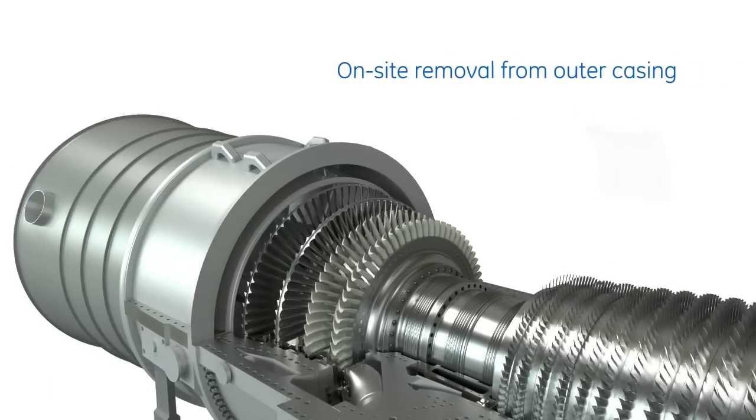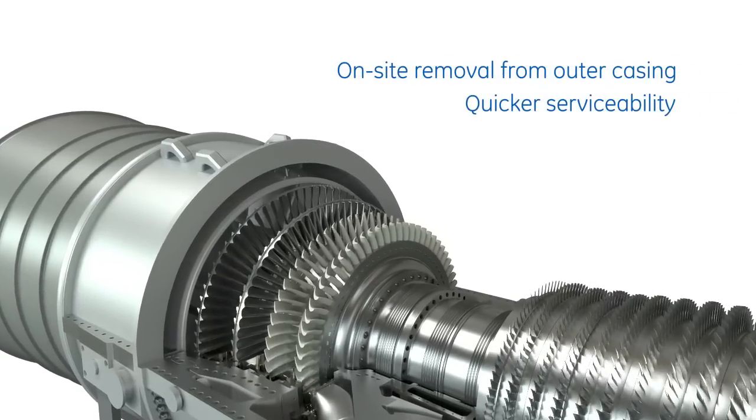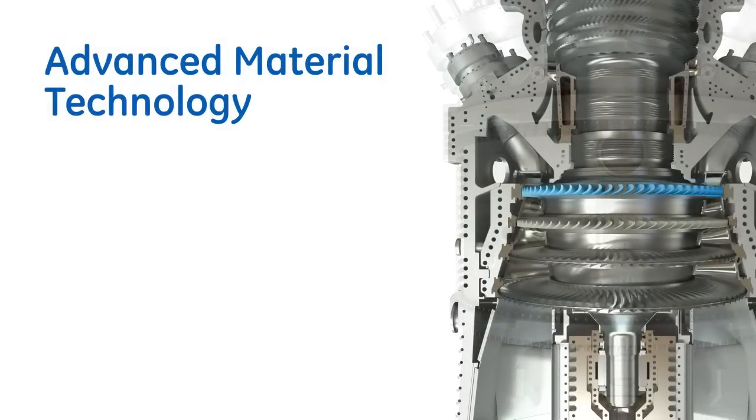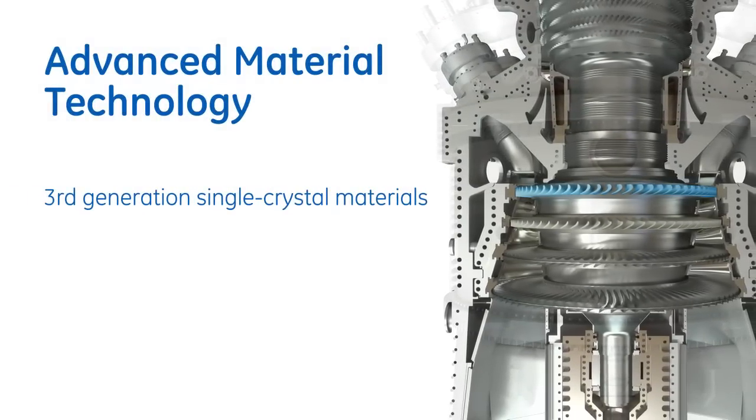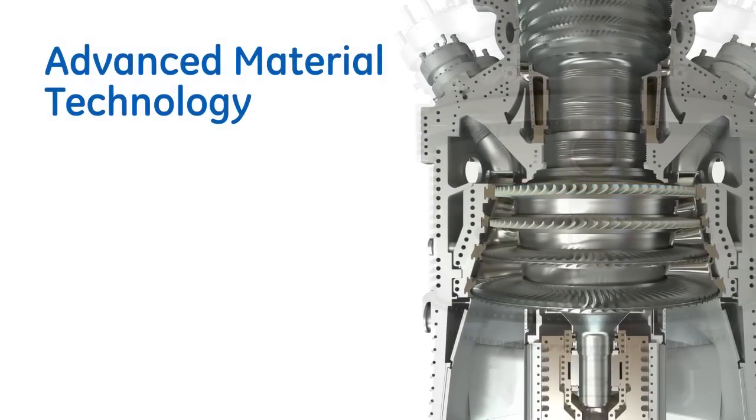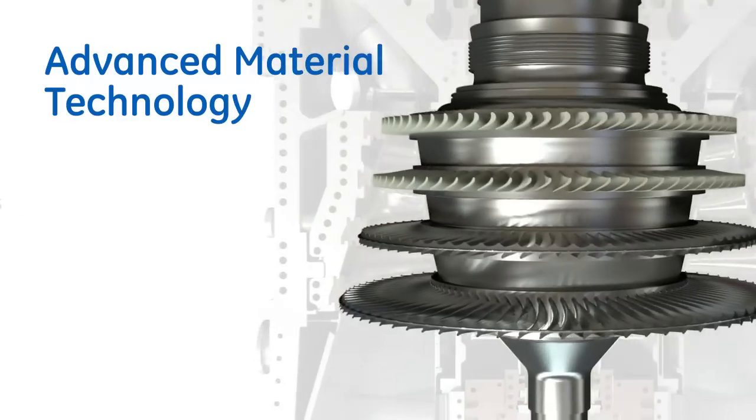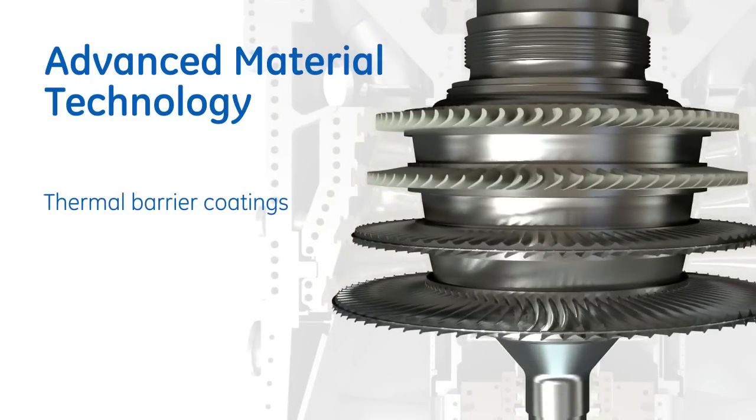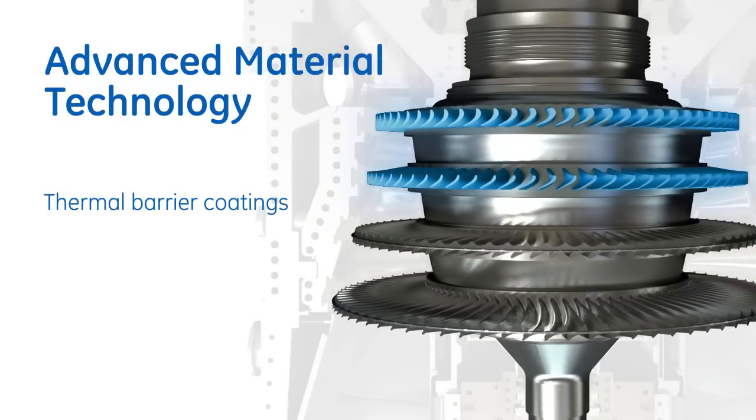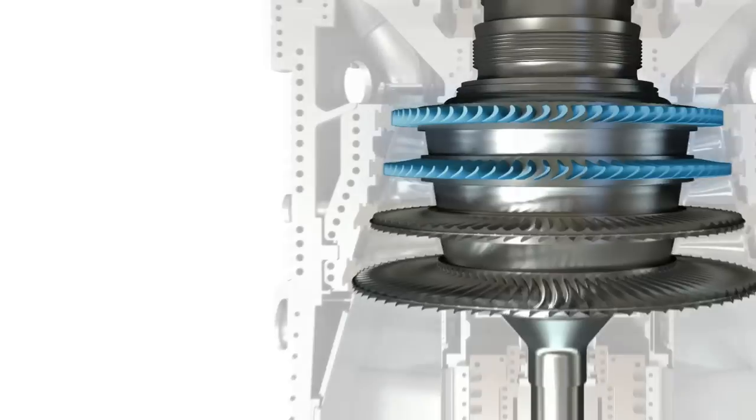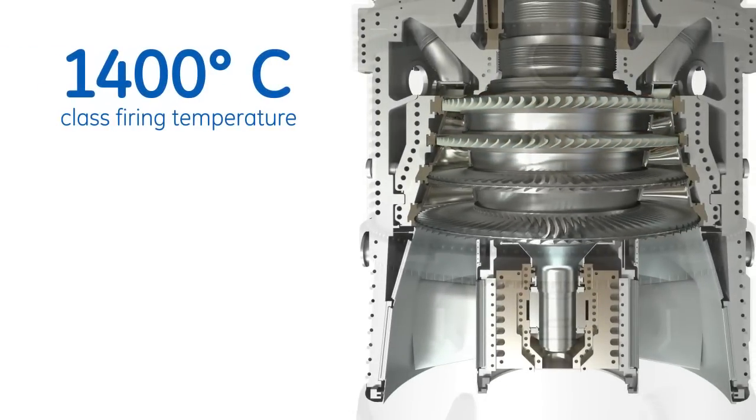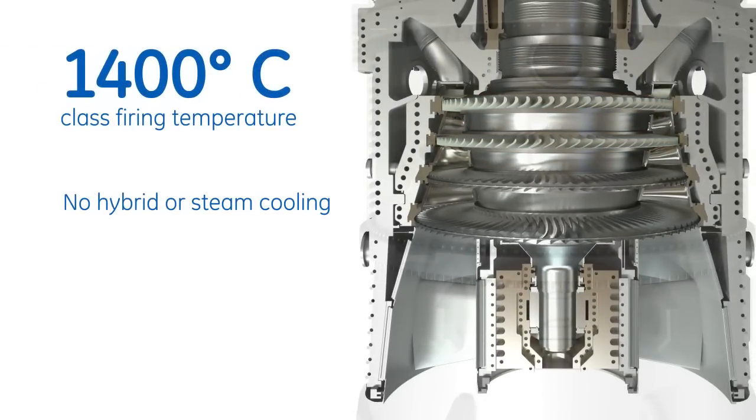The two-piece inner shell can be removed from the outer casing on-site by rotating it out. Stage 1 buckets consist of third generation single crystal materials. The other stages employ directional solidified material for buckets and equiaxed nozzles. Thermal barrier coatings are applied to all stage 1 and 2 buckets. These materials allow for increased firing temperature capability without the need to apply hybrid or steam cooling.